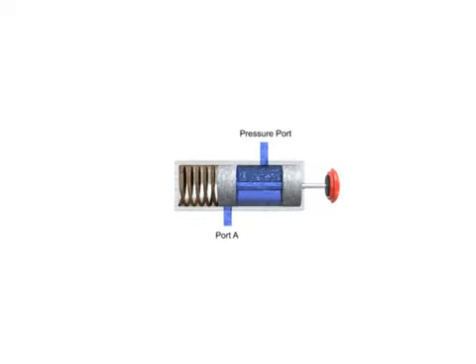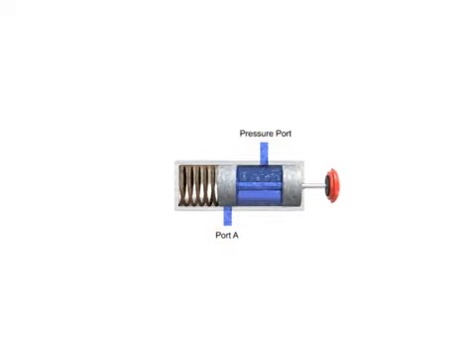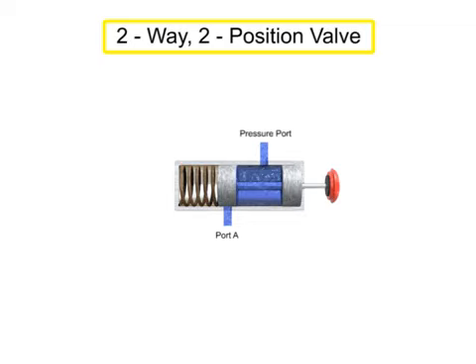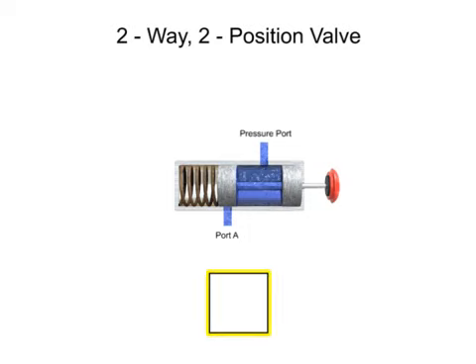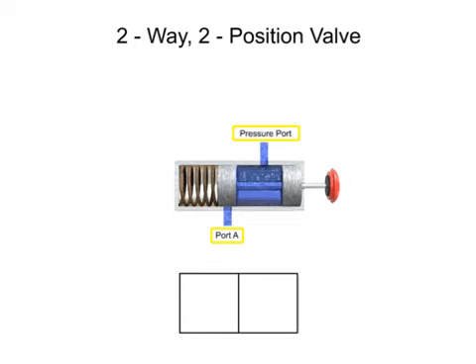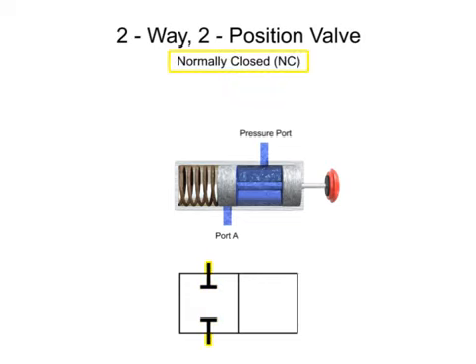Here is a similar valve to the one previously shown. It has two ports and two positions, so it is also a two-way, two-position valve. To illustrate the differences, let's build its graphic symbol. It is a two-position valve, so the graphic symbol will have two adjacent boxes. This valve also has two ports; however, in the normal non-actuated position, both ports are blocked. Therefore, it is a normally closed valve.